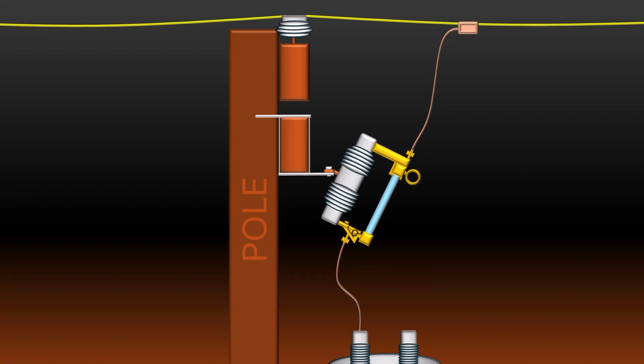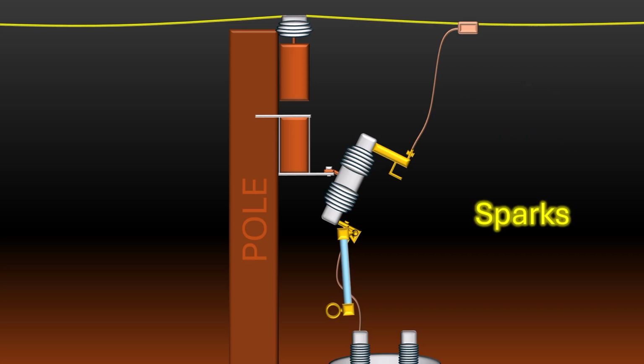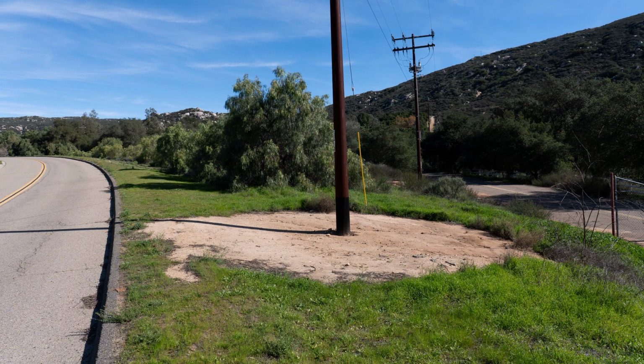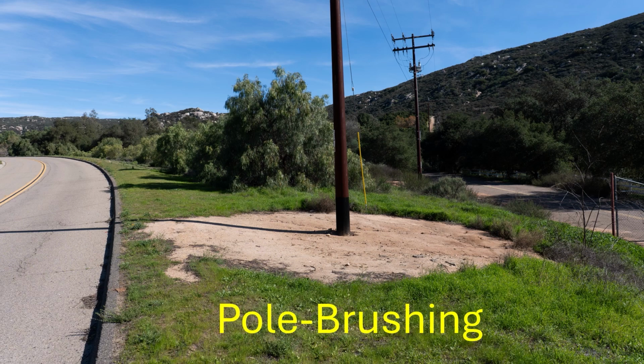Let's take a look at that one more time, a little slower. You'll notice that when the fuse element blows, sparks of molten copper and other metals are ejected from the fuse holder. This is pretty common with some of the older fuse holders. These sparks also have the potential to land on the ground and start a fire. For that reason, some utilities engage in a practice called pole brushing, where they clear the vegetation away from the base of the pole where the sparks might land. They also utilize newer fuse holders that are able to suppress the sparks and prevent them from leaving the fuse holder altogether.